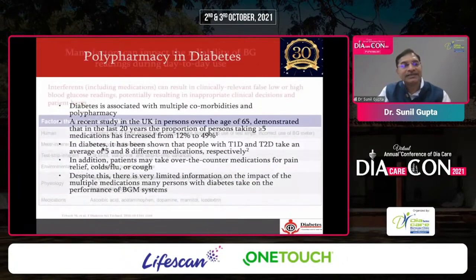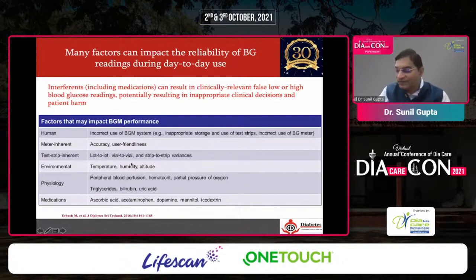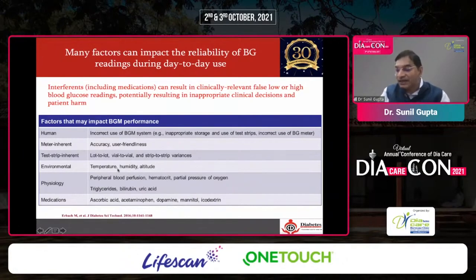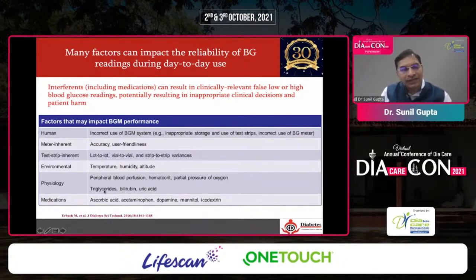There can also be inherent error in glucometer accuracy, lot-to-lot strip variations, and environmental factors. At higher temperature or high altitude, blood glucose readings may appear elevated. High humidity can sometimes cause falsely low readings. High triglycerides can cause false low readings; high uric acid can cause false high readings; high bilirubin can cause false low readings. Many drugs can also interfere with blood glucose readings, giving falsely high or falsely low results.